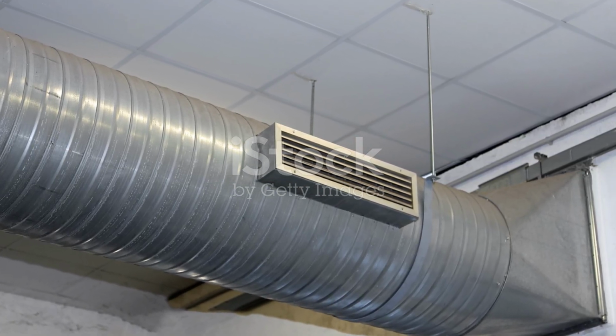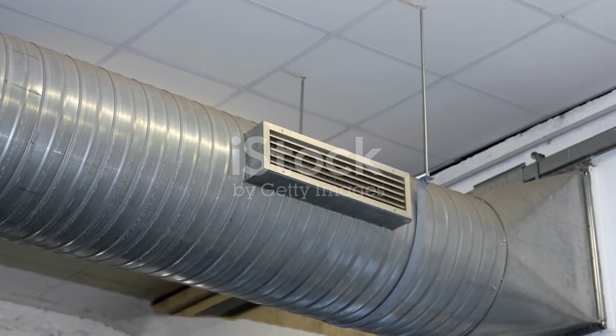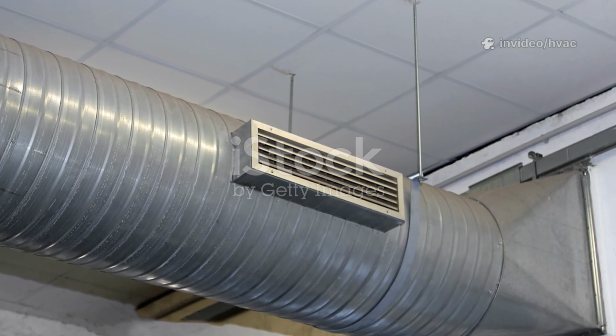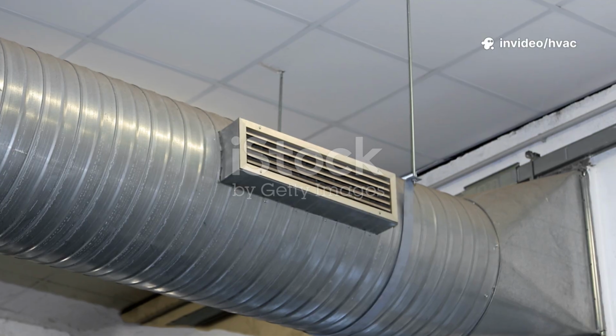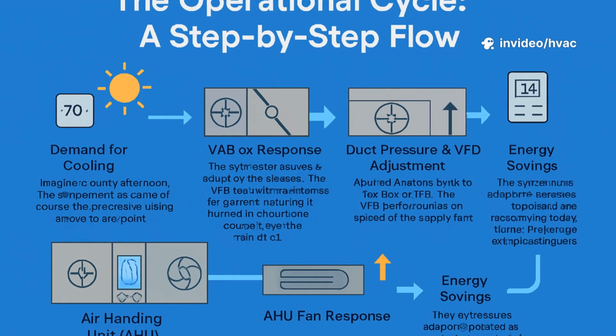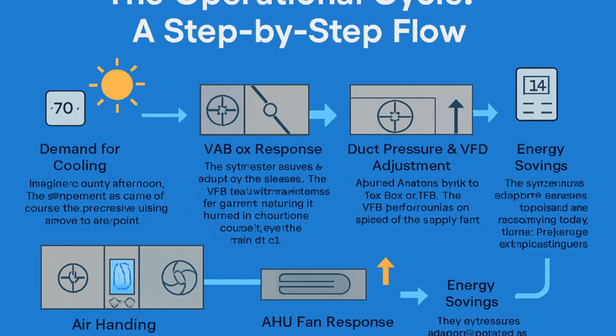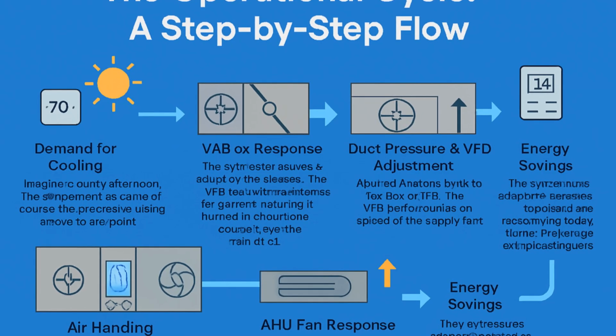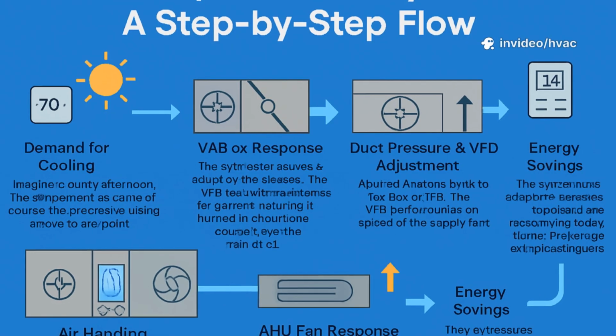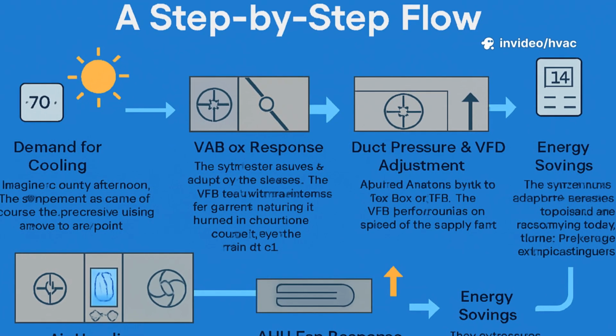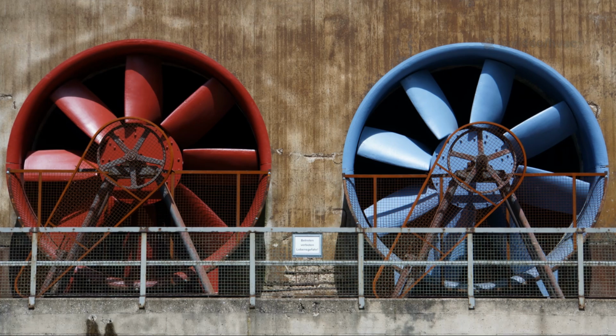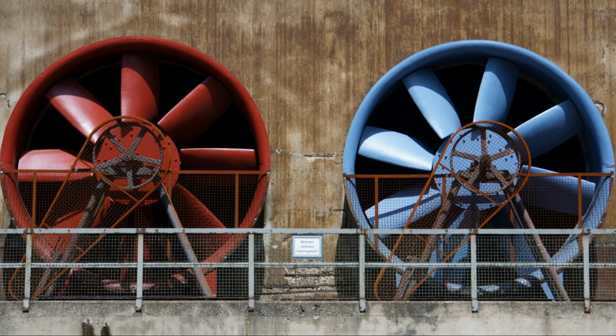As these dampers open, they draw additional air from the main supply duct, which causes a slight drop in air pressure inside the ductwork. A sensitive pressure sensor installed in the main duct detects this subtle change. It's constantly monitoring the system, and when it notices the pressure drop, it immediately sends a signal to the variable frequency drive, or VFD, that controls the main supply fan. The VFD responds by ramping up the speed of the main fan.